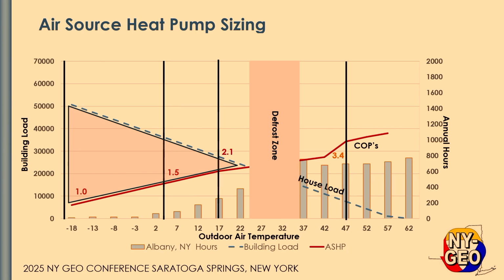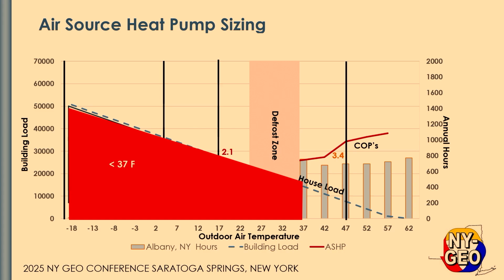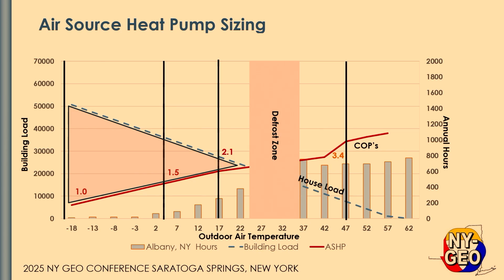I do have the defrost zone here, so from 37 to 25. Roughly in this zone is where you're going to be running defrost. So if you shut the equipment off, essentially all of this area is electric heat, or if you're dual fuel, it's going to be a furnace backup. So you've got a lot of hours in that area that you're going to have to make up. And that's, as I said, kind of the old school way of doing it, and probably disappearing to a certain extent, but I think there's still a lot of systems out there that do that.